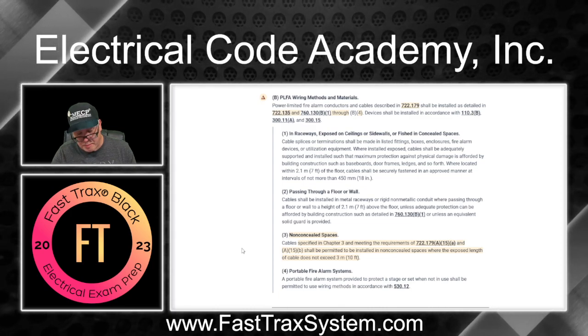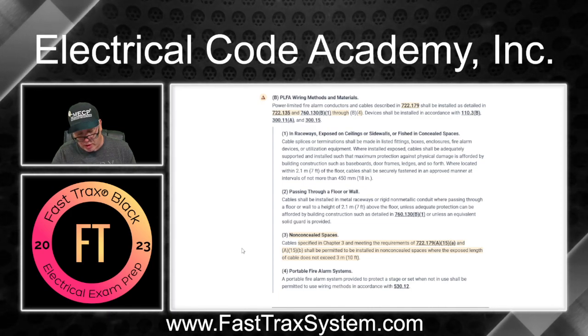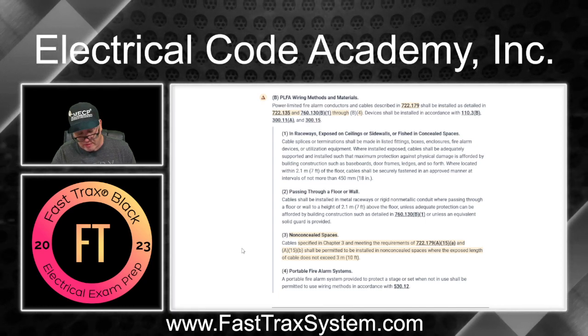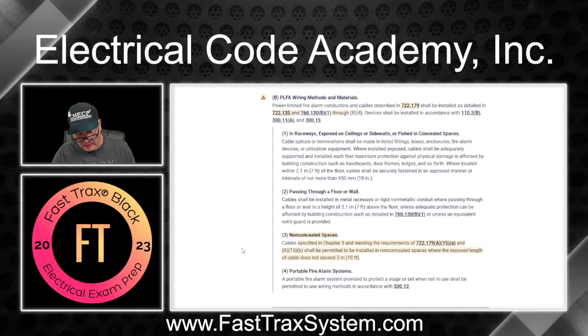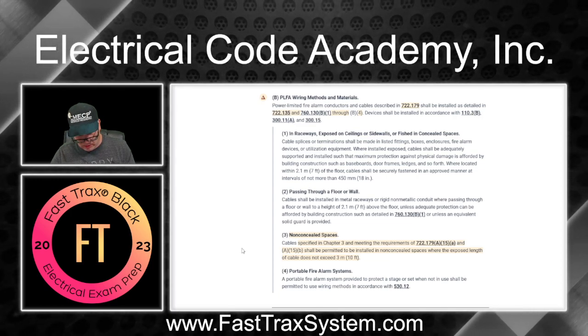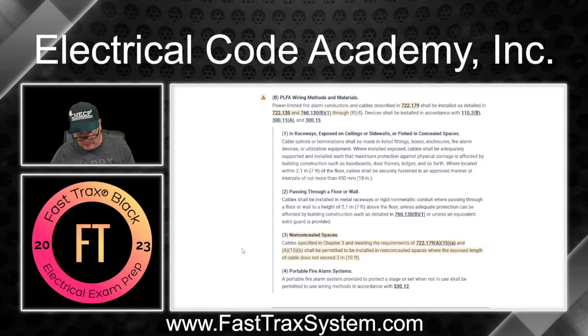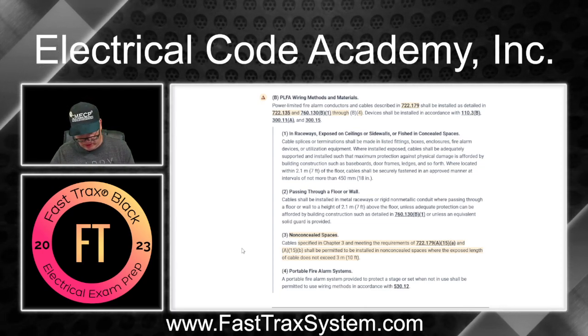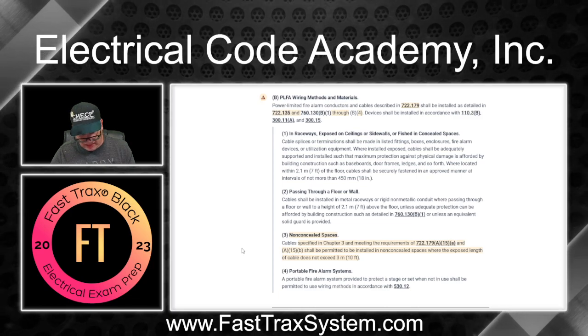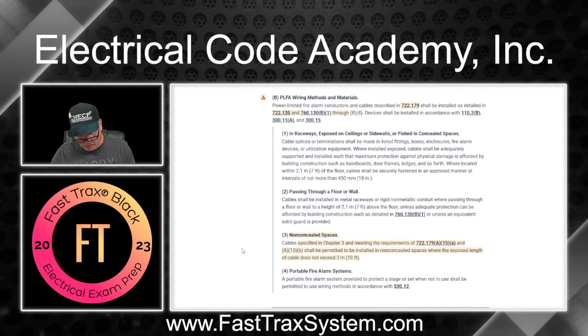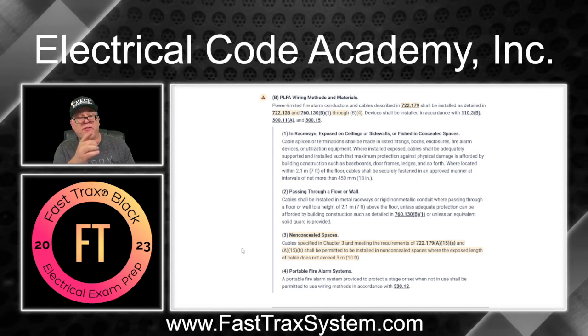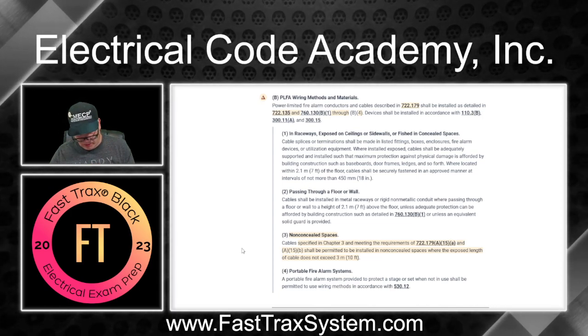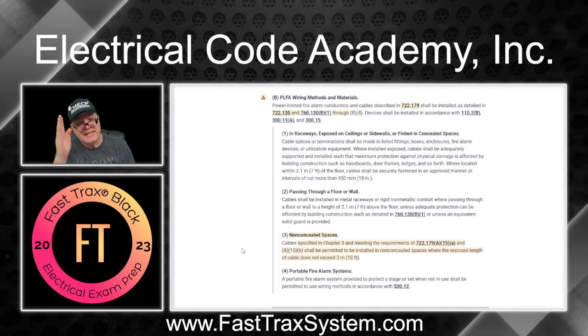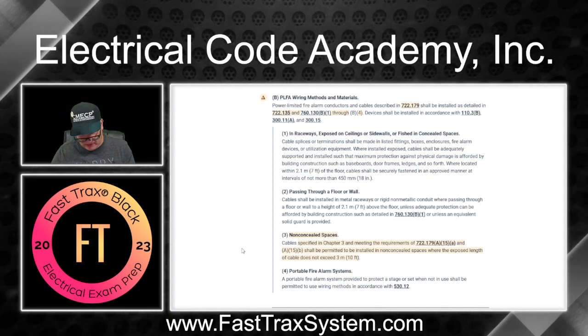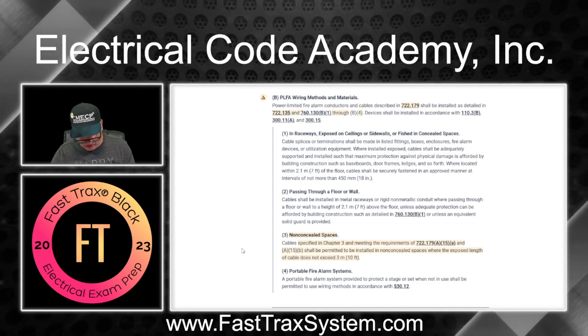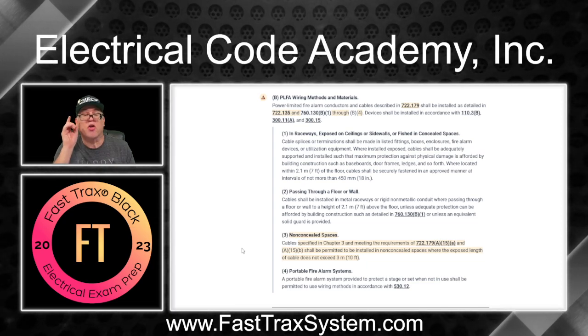Okay, non-power limited circuits, 760 part 2. And then we see conductors, 760.49(B). Okay. And I'm just going to keep looking to make sure. Power limited, and I guess our question was for power limited. You go down, you'll see power limited, not non-power limited, power limited. That was our question. And that is part 3. Now, under part 3, if you're following along in your code books, folks, you see where the references are indented. That means they're germane to the power limited. And you go down and you'll see conductors size 760.142, a great place to start.